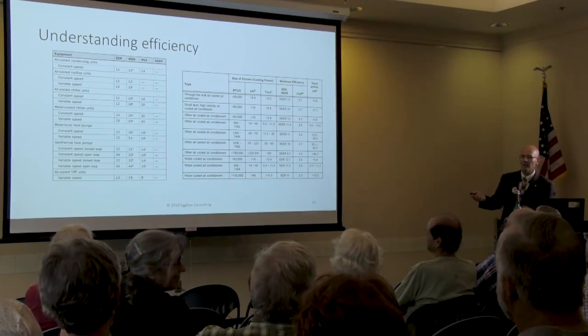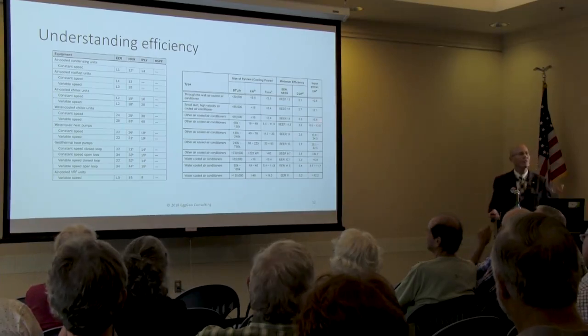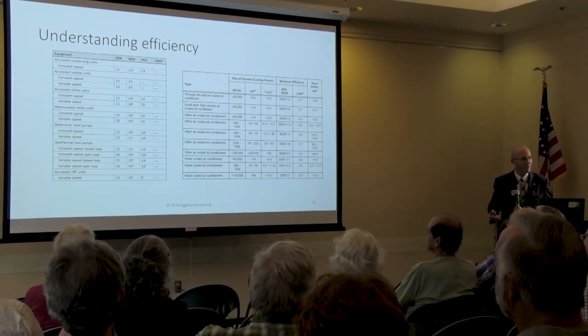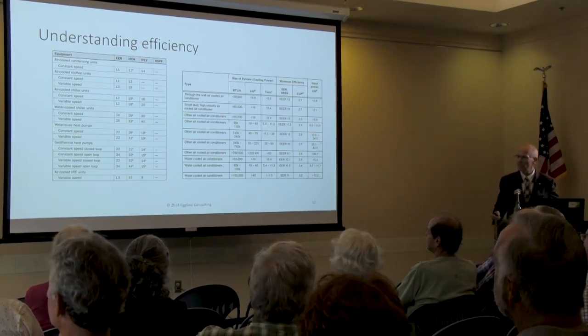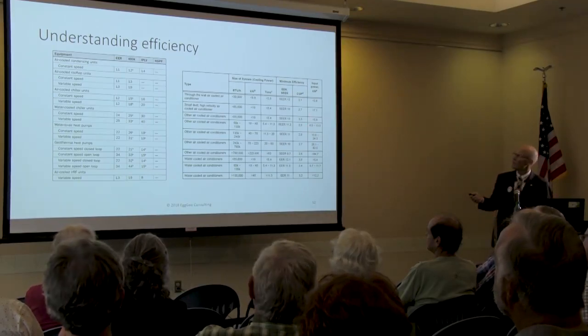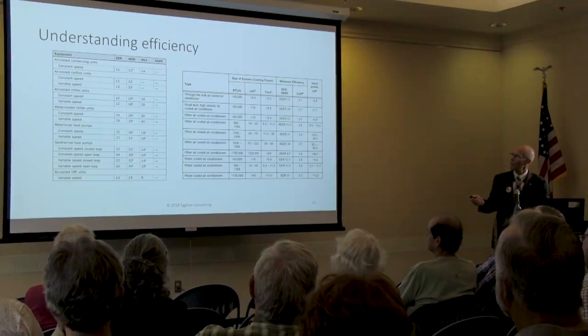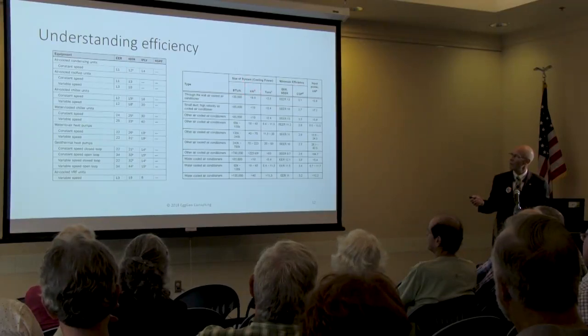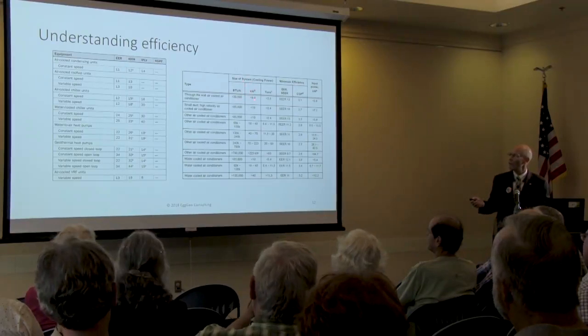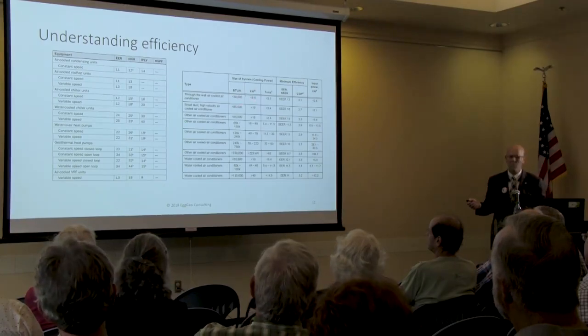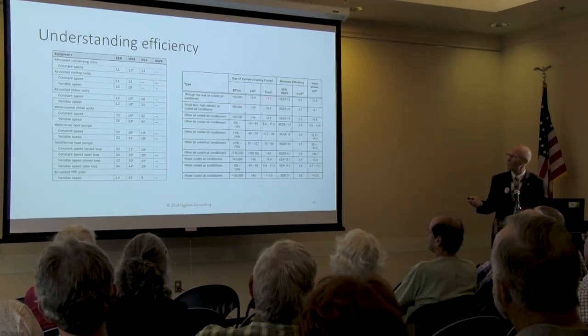Just to give an example of what you will see when you look at an equipment chart of different and various air conditioners and heaters, this can be very confusing. You're looking over here, okay, I've got a system size or cooling power of 30,000 BTUs. It says 8.8 kilowatts. It says it's 2.5 tons. What does all this mean? Well, I just talked about tons. That's 12,000 BTUs. If you divide 12,000 into 30,000, that's 2.5. So it's a 2.5 ton unit.